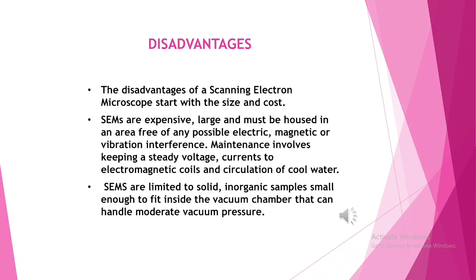The disadvantages of the scanning electron microscope start with size and cost — it is very expensive, large, and must be placed in an area free of possible electric, magnetic, or vibrational interference. Its maintenance involves keeping a steady voltage and current to electromagnetic coils and circulation of cooling water. SEMs are also limited to solid, inorganic samples small enough to fit inside the vacuum chamber that can handle moderate vacuum pressure.